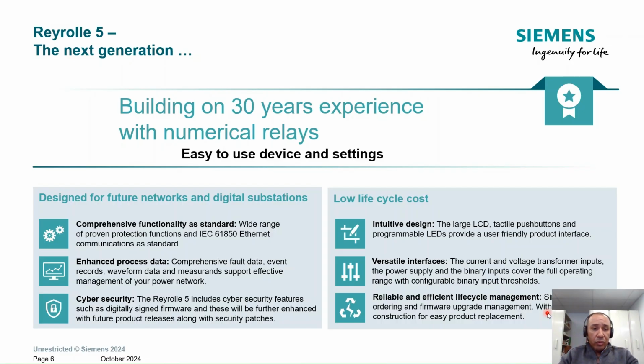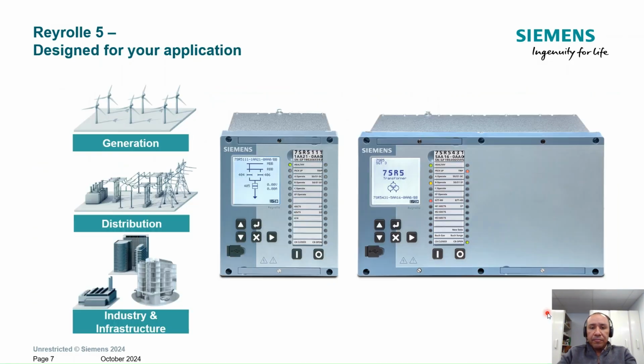And also the comms, whether the device is going to come with RJ45 or fiber, and whether the device needs to have arc flash. These are the three things that you need to order when you set the part number of the device. Everything else comes as standard: protection functions, communication protocols, universal power supply, and 1 amp and 5 amp CT. These are the points that you don't need to worry about.